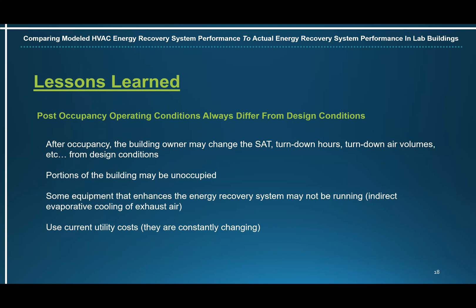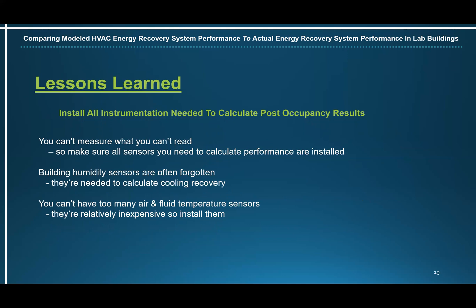Use current utility costs — from the time a building is designed and modeled until it's actually occupied, there can be significant changes in utility costs. Install all instrumentation needed to calculate post-occupancy results. You can't measure what you can't read, so make sure all sensors needed to calculate performance are installed. Building humidity sensors are often forgotten, and they're needed to calculate cooling recovery. And lastly, you can't have too many air and fluid temperature sensors — they're relatively inexpensive, so install as many as you need.